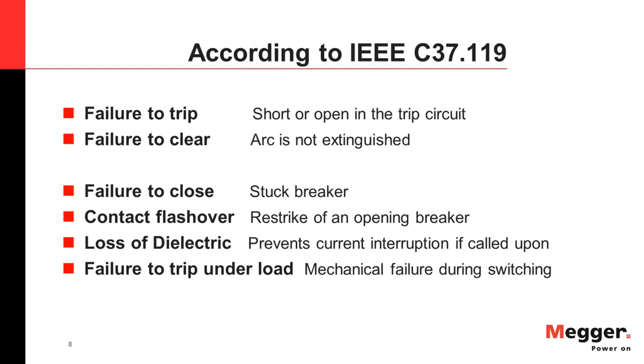The second category for Breaker Failure is Failure to Clear, which means your tripping coil is energized, your breaker is opening, and your 52A contacts get picked up. So you can see everything happening, but the arc is not extinguished — the arc is still there. That is also a Breaker Failure, called Failure to Clear.